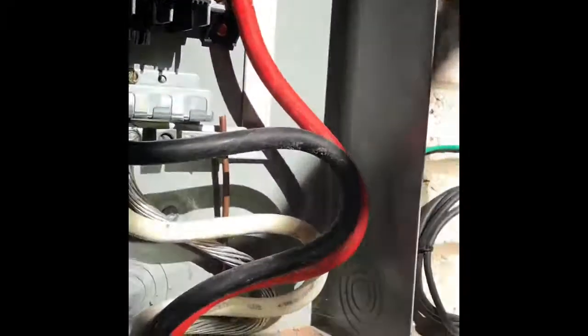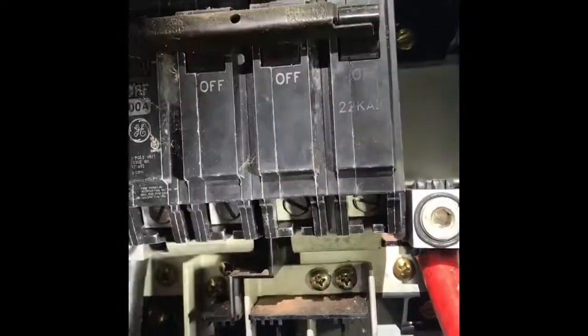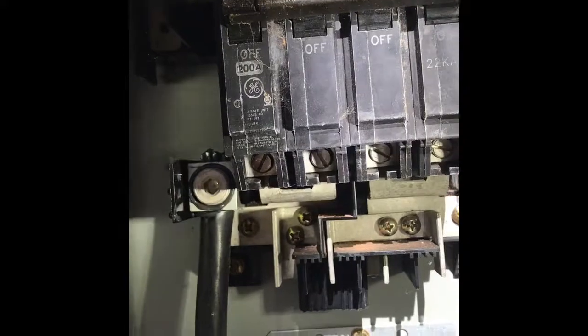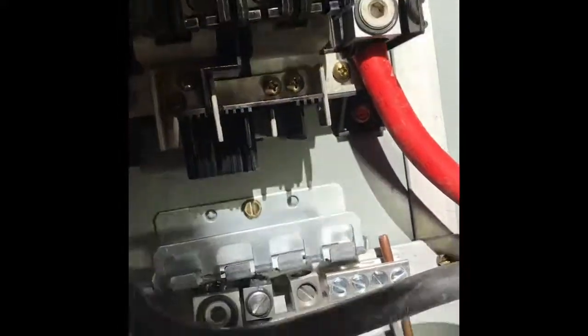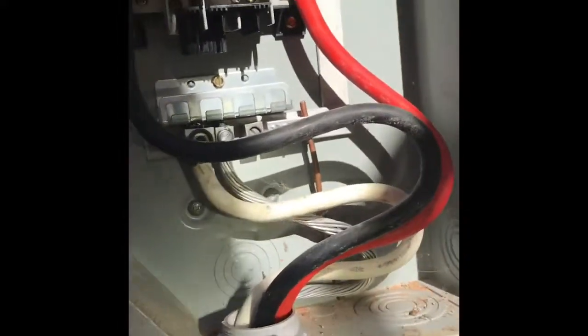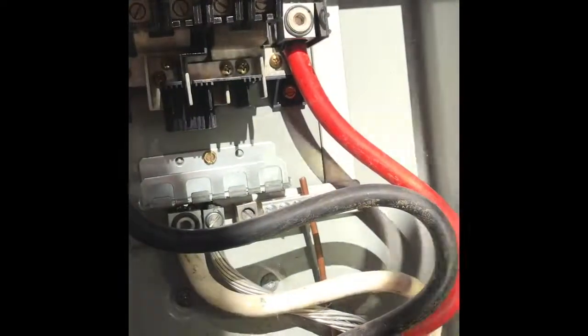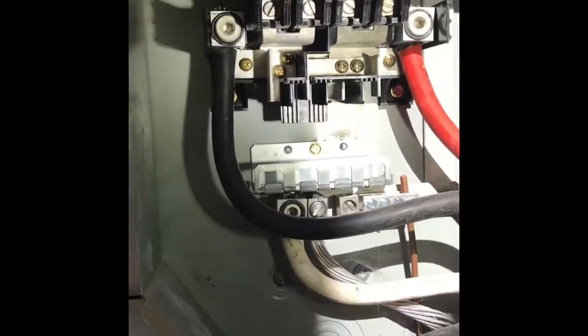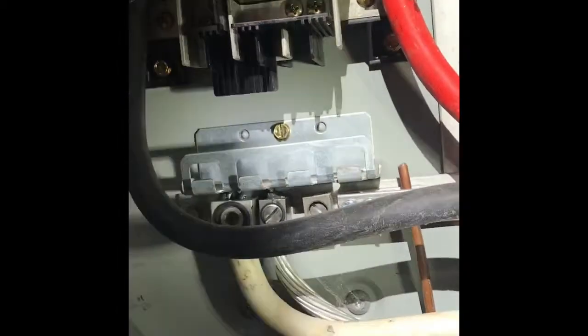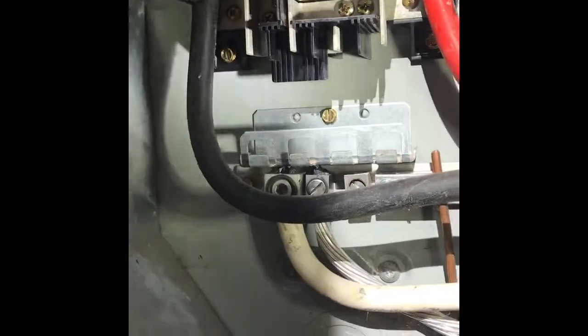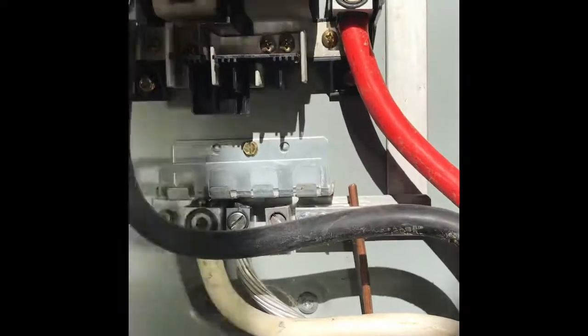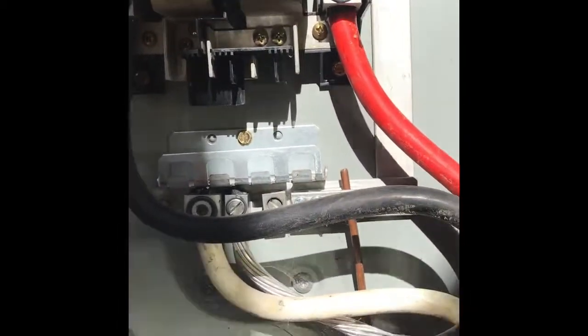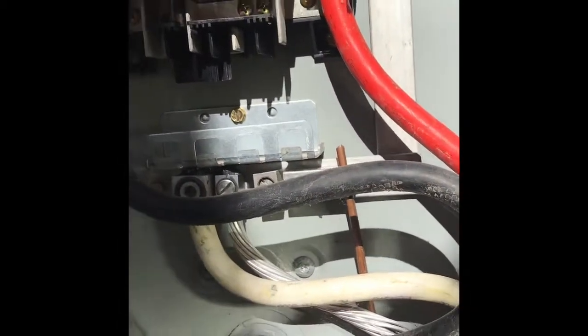A lot of times in Tennessee you'll see at your electric meter base, especially if you're underground service, that you'll have a box underneath it, usually with a single 200 amp breaker in there. What that usually is, sometimes just an outside disconnect, but typically what that means is the distribution panel inside the home is greater than, I'm not going to quote it because all kinds of jurisdictions are different, but typically greater than 6 feet, meaning from where the meter runs into the house, where the main panel is in the house is further than 6 feet away.